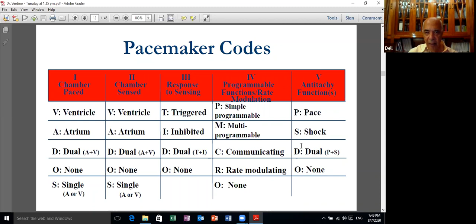Now let us spend some time on the timing of the pacemaker, which is a very important subject. In the VVI, which is a ventricular inhibited pacemaker, we program something called the lower rate limit. It is the rate beyond which the patient goes with his native rhythm, and under this rate the pacemaker starts to pace. So here we have an ECG, and here we have a ventricular electrogram. There is no atrial electrogram because this pacemaker does not contain a lead in the atrium. It contains one single lead in the ventricle.